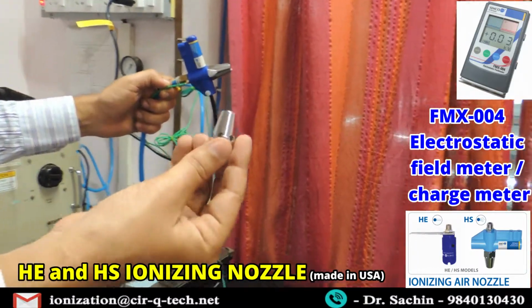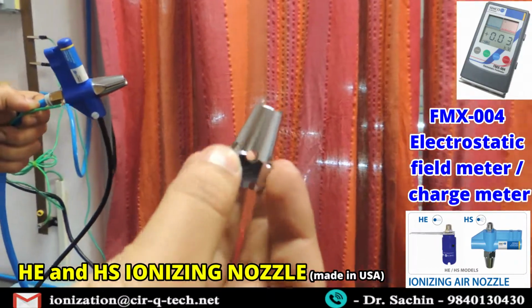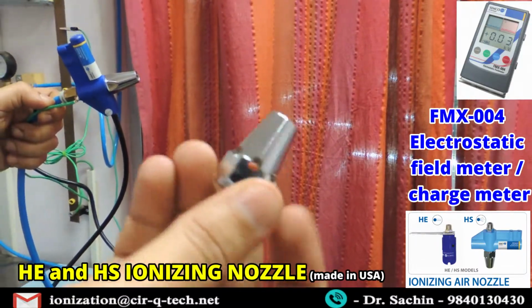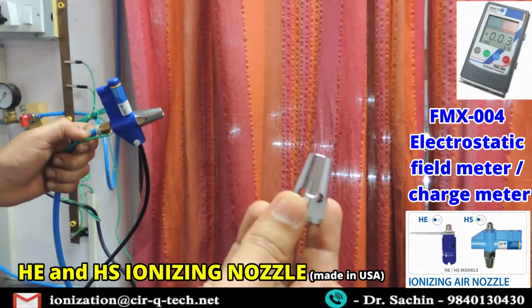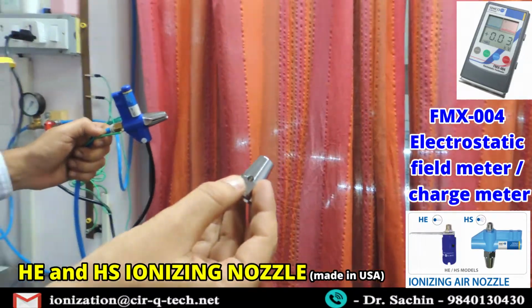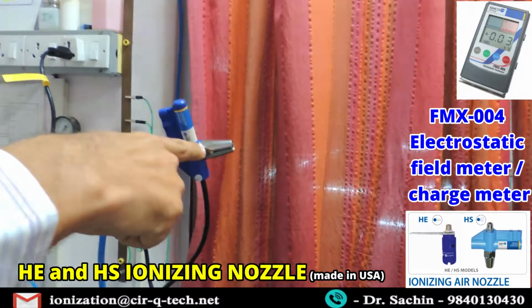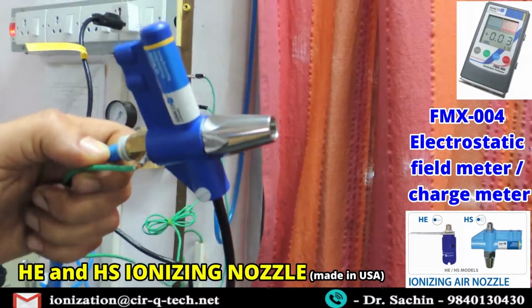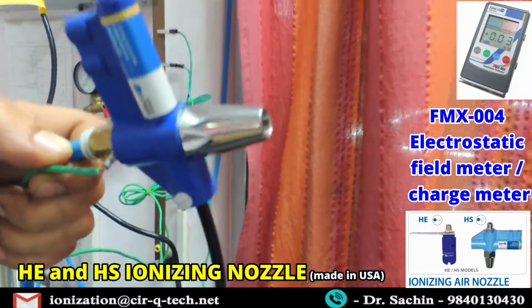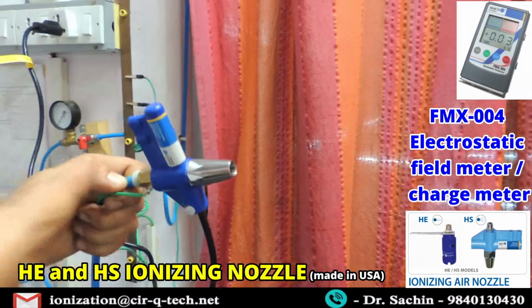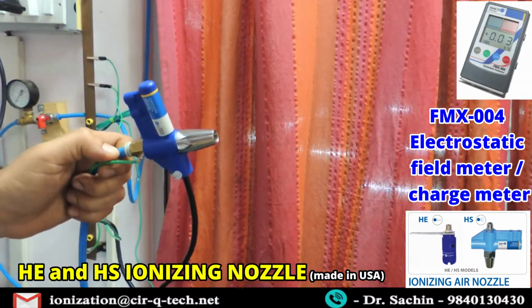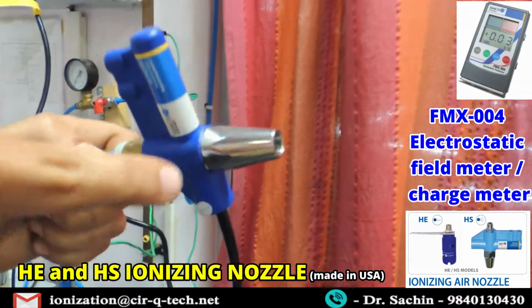The standard HS nozzle comes with this flare. You will be able to see this kind of holes. This is the standard nut, the nozzle opening nut. It will have the flares. But you can also order a special kind. Let us say you are working in an area which has a lot of powdering material, and your emitter pin tends to attract that powder, so you can use this particular nut.